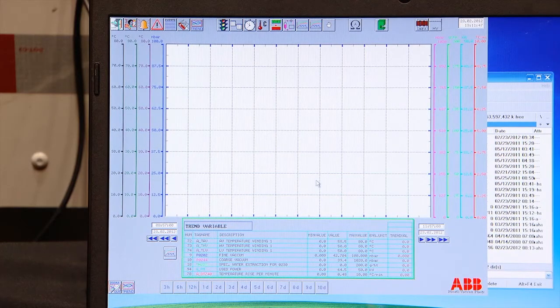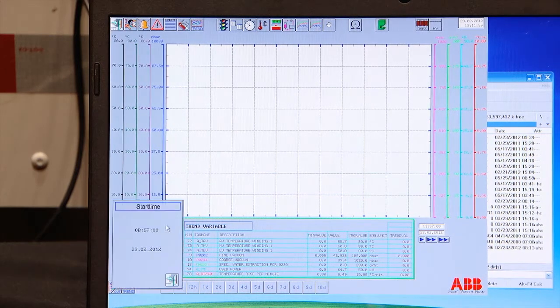The trend curve looks empty, but you have to set the initial time when you started the process. You do it by clicking here on the time. Start time, click on the numbers and increase them. It was about 1 o'clock when we started. Maybe a little bit less. We take 12:50. Okay, click on the date, set OK, and exit.